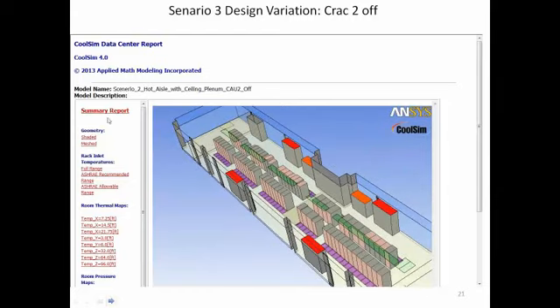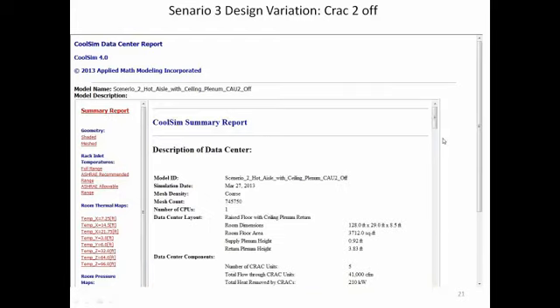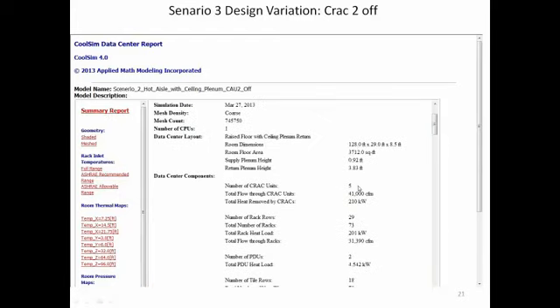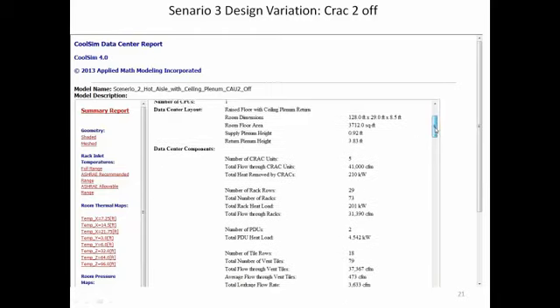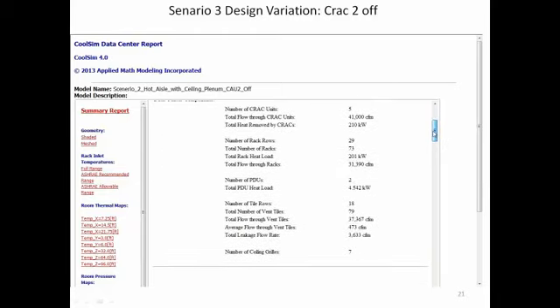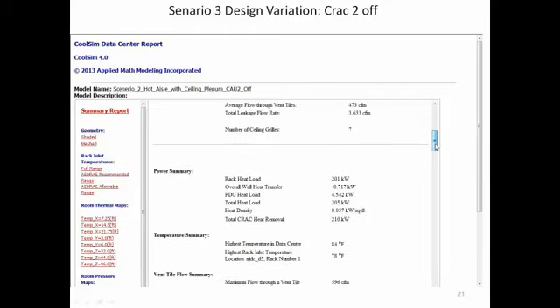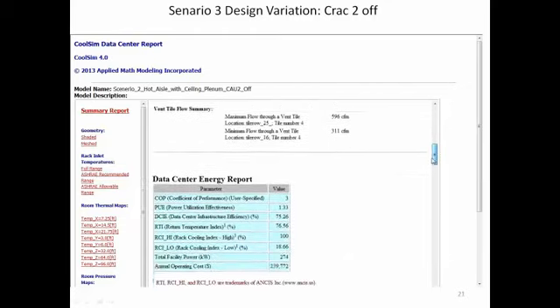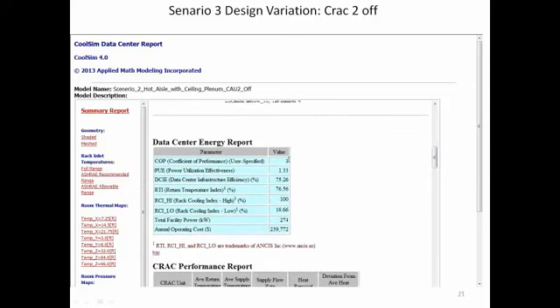We had too much. So if we take a look at the summary report now, we can see that the flow through the CRAC units is 41, and that's come down from 52. So now we're much closer to the 31 that we need to be. That's going to save energy. So the COP is now up to 3. That brings the PUE down to 1.3. We're getting respectable now. Look at the RTI. The RTI came from the 60s, 69, 70, up to 76.